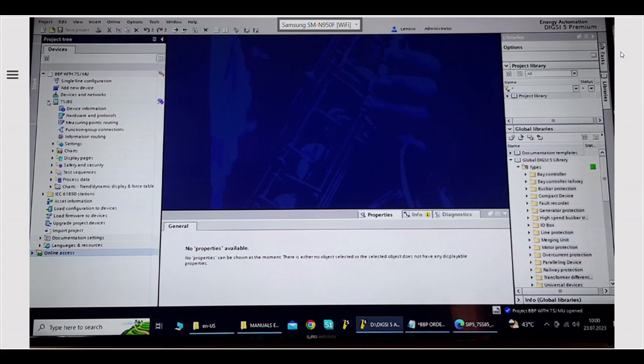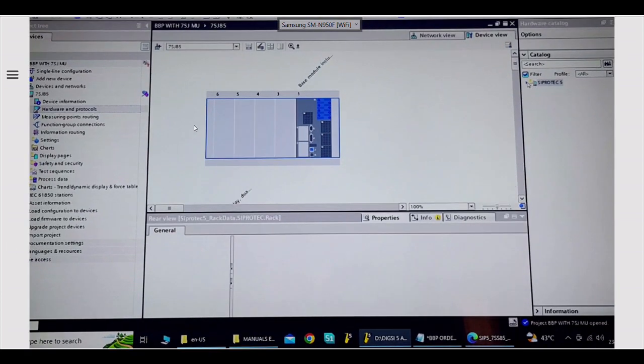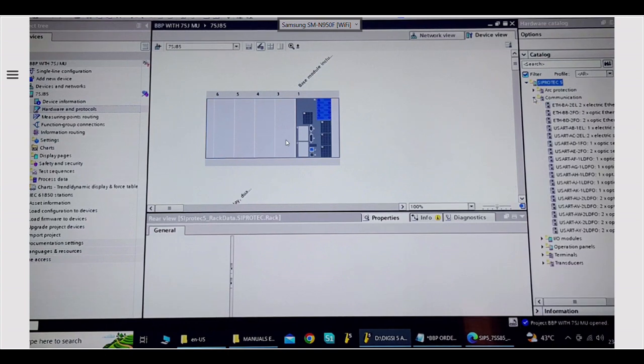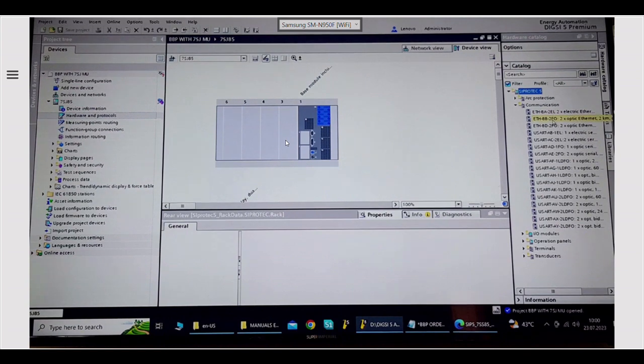There is one precondition for using this relay. In the communication part, we have some communication ports. Names are here. This is for standard IEC station. But for busbar protection, we can use on the port, not B1. If we have this port, then we can use this bay unit as a bay unit of the busbar protection, otherwise it cannot be used.